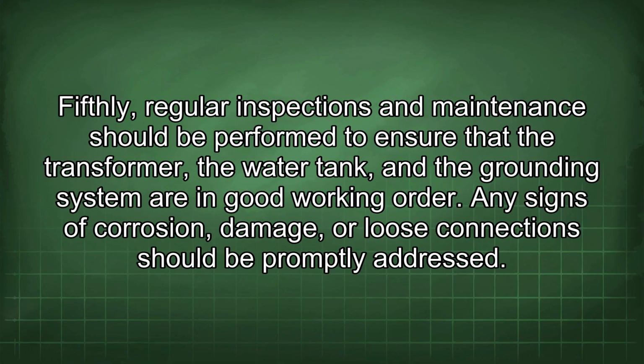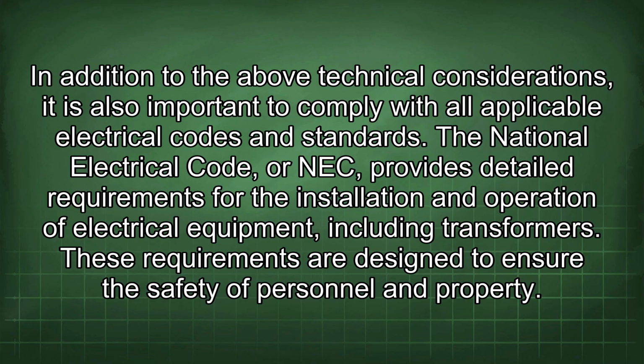Fifthly, regular inspections and maintenance should be performed to ensure that the transformer, the water tank, and the grounding system are in good working order. Any signs of corrosion, damage, or loose connections should be promptly addressed. In addition to the above technical considerations, it is also important to comply with all applicable electrical codes and standards. The National Electrical Code, or NEC, provides detailed requirements for the installation and operation of electrical equipment, including transformers. These requirements are designed to ensure the safety of personnel and property.